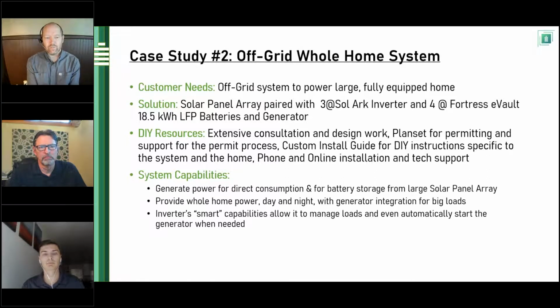Yeah, that's a great question. So with that inverter in particular, Sol-Ark, as well as an Outback Radian or a Schneider XW, those are 3 of the big heavy hitters in that segment. Any of those can just be reprogrammed, so you're not replacing equipment. If someone says I want to be off grid, which in some regards is necessary, in other regards people just want it, so go for it. If you decide 6 months later that it's not really a great idea and your utility power is still on site, you can just change the programming. It's as simple as that. So you can do grid tie, you could do grid assist, where you're just using them as a charging source if your system's not keeping up, or you can pull the wire out completely and be off grid. All with the same equipment.